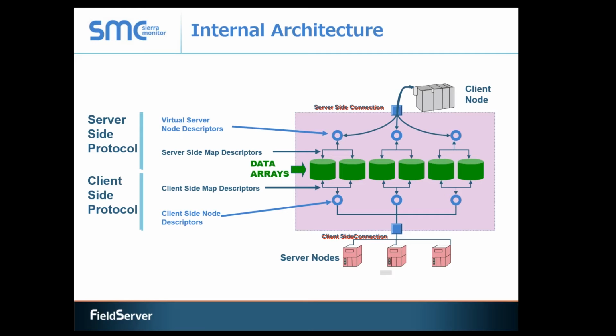But hopefully this video will at least provide you with the backbone needed to put the various pieces of the information provided into place. In order to make this more understandable, we'll use an example of a Modbus to BACnet configuration where we're reading 3 Modbus devices through an RS-485 port and then serving that data up into BACnet IP.